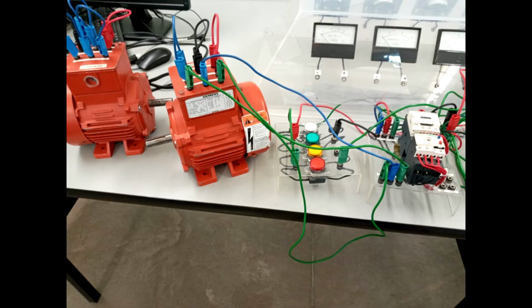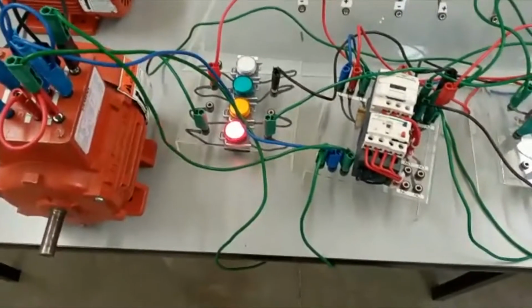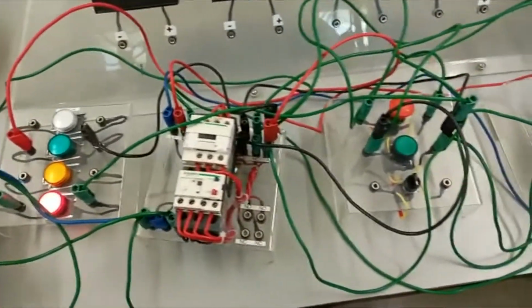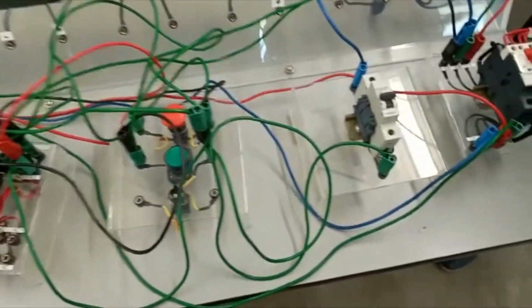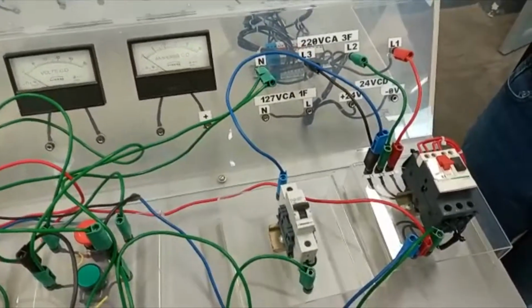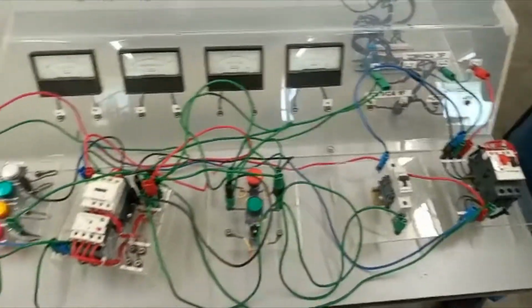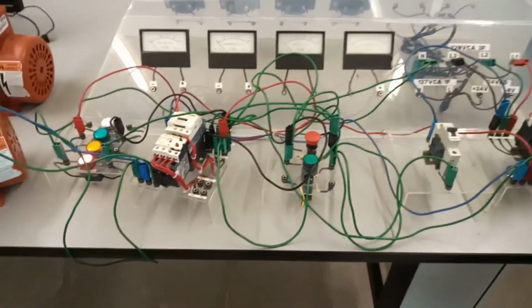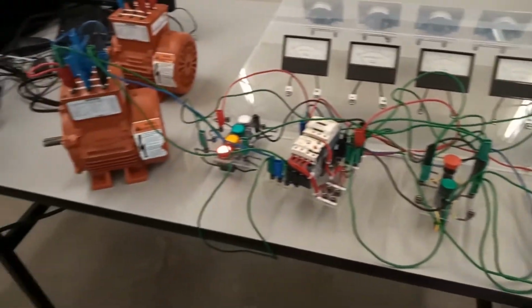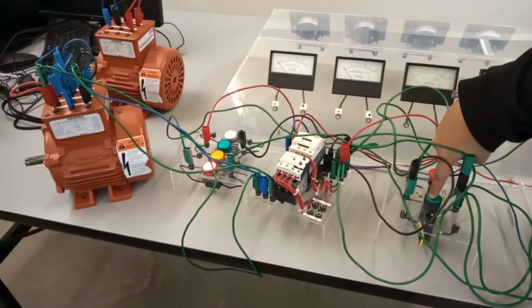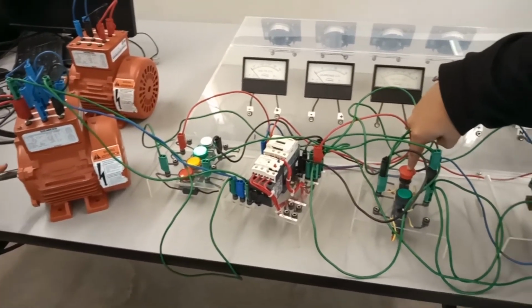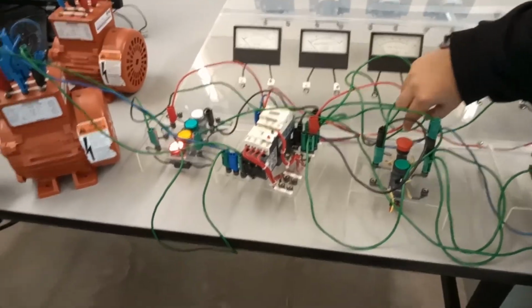Table implementation. This implementation is an interpretation of the previous one, so the functionality is practically the same. The only variation is that in this section the two voltage connections of the motor were used, low voltage and high voltage. These connections of the motor can be seen on the motor or in a manual too. In this implementation, to control the direction of the motor, lines 1 and 3 were inverted and the spin of the motor was inverted.